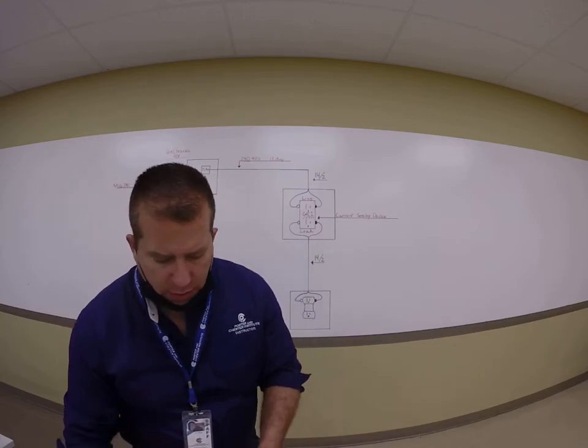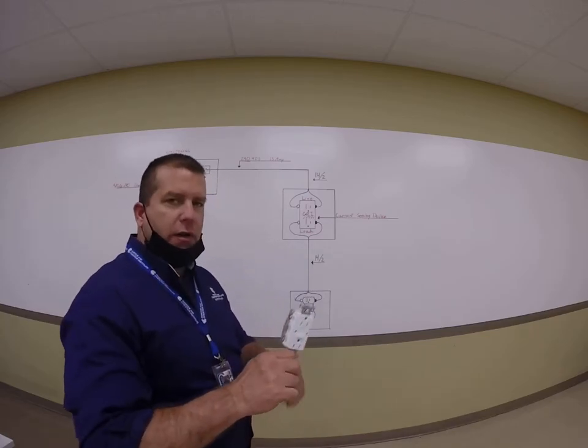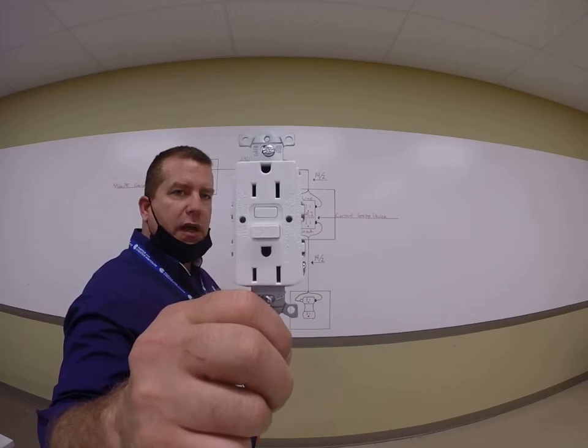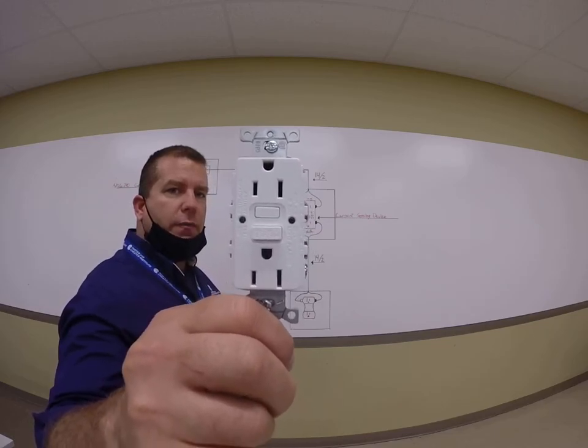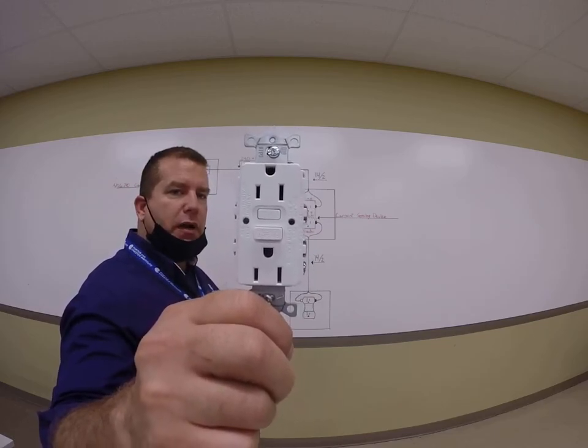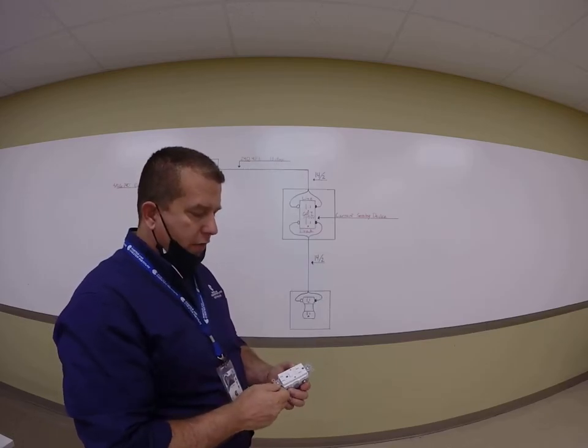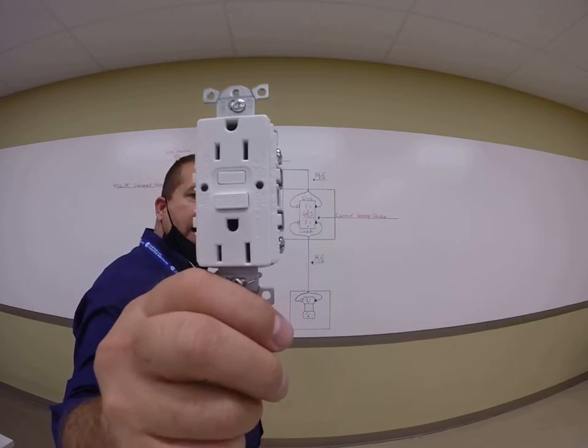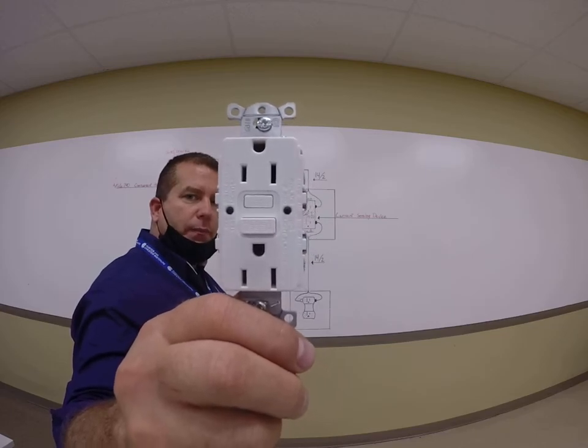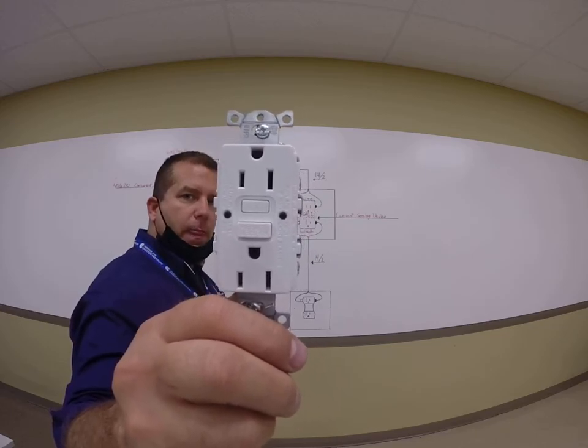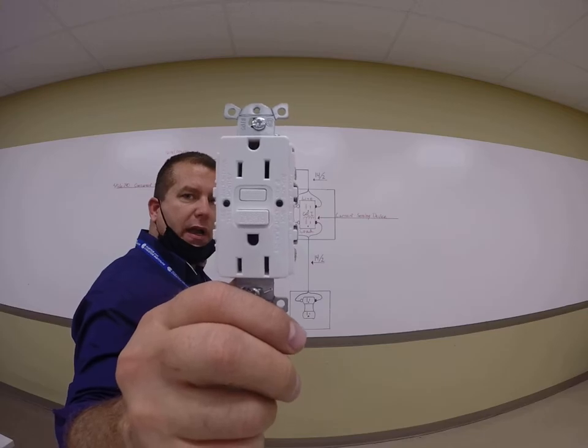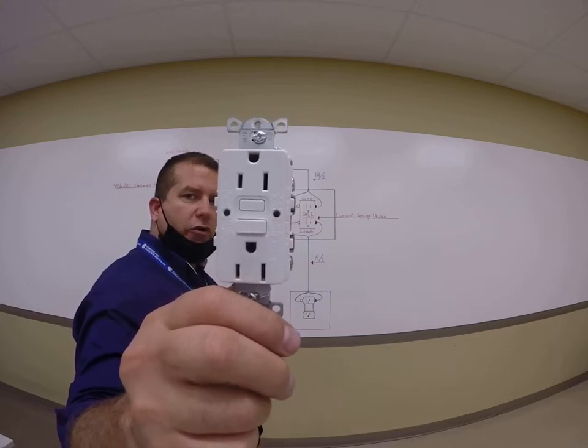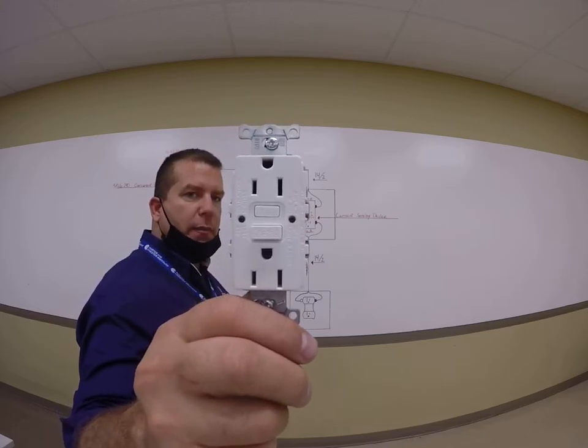But there's a couple things I wanted to cover on this. So if we get a good close-up shot of this, we see the GFCI. We've all seen these before. They've got a test and a reset button on them. And on this particular one, you've got lights. So the two little dots left and right in the middle of the receptacle. One will be green if it's reset and on, and then the other one will turn to red if it's tripped, and then the button will pop out.